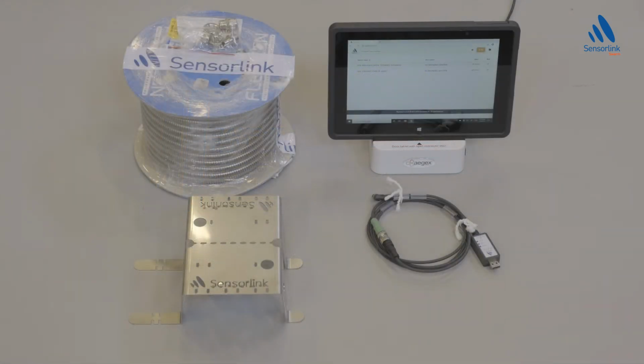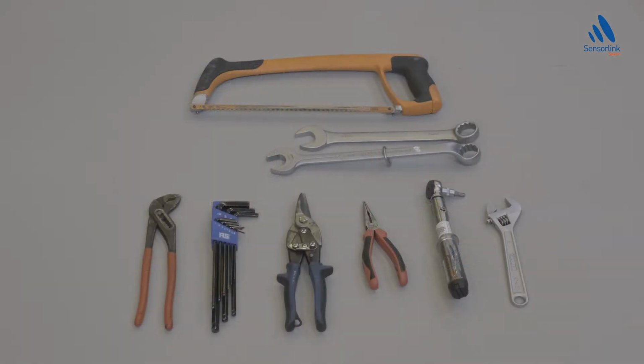After mounting the Swarm S1 sensors to the pipe, they need to be configured using the USB cable and a tablet or PC having PipeView software installed on it. Tablets can be procured from Sensorlink in both EX and non-EX versions, and they come with the latest PipeView installed. If the sensors are installed in the EX zone, there is an EX requirement to physically protect the sensors and the cabling. This is done by installing the protective covers over the sensors and using conduit over the cabling. These are the tools necessary to install the Swarm S1 sensors, and as you can see, there are no special tools required.